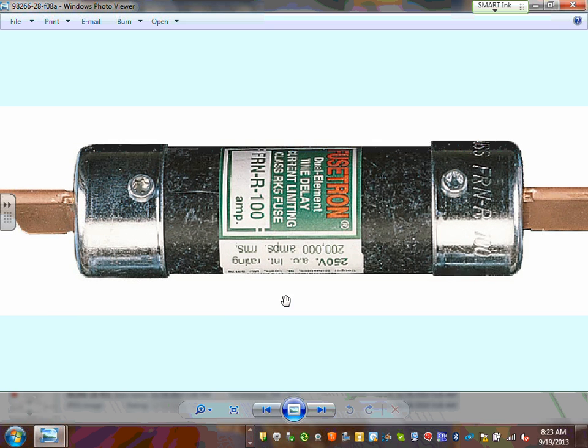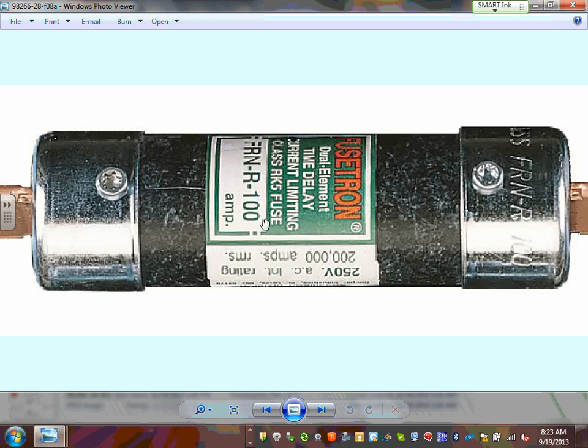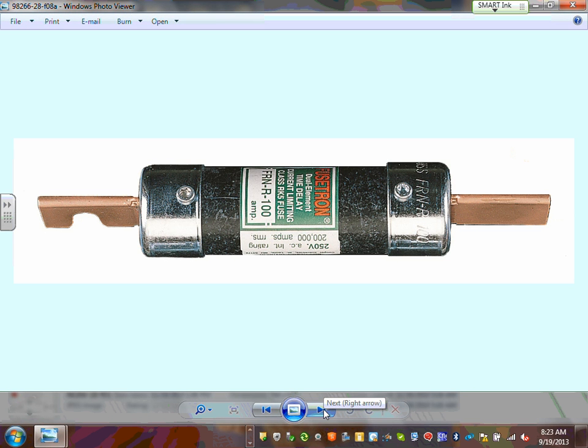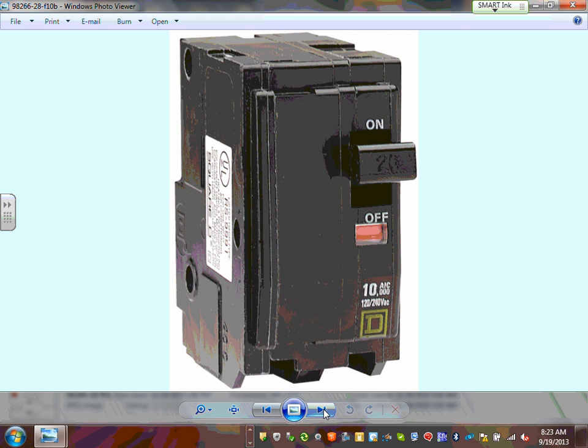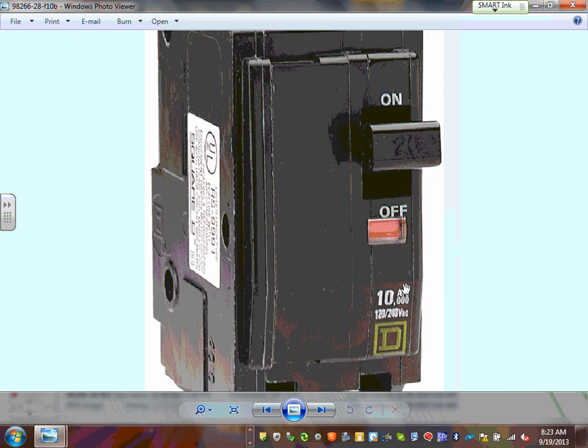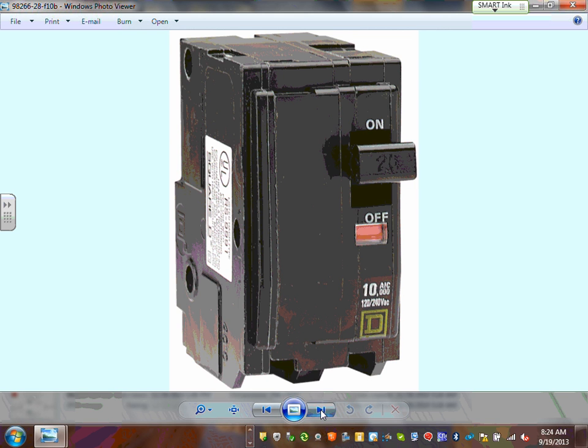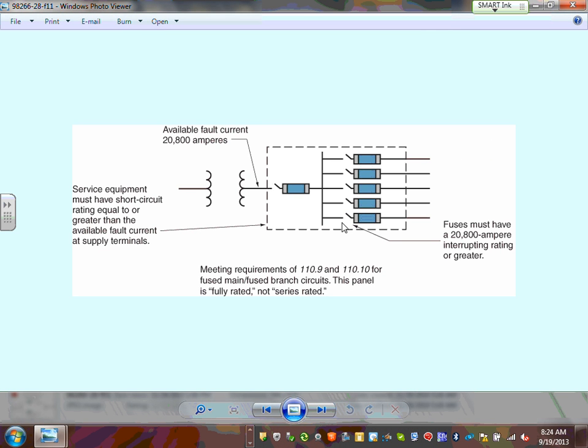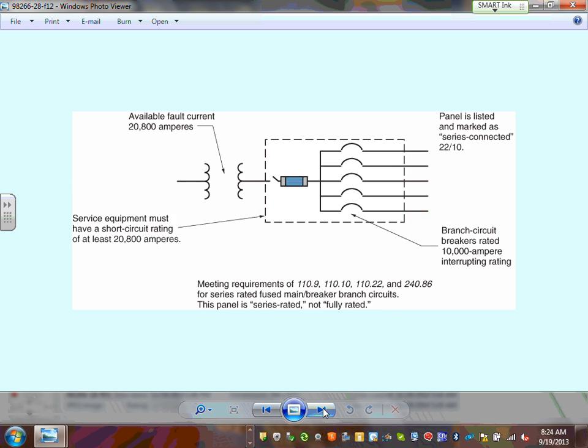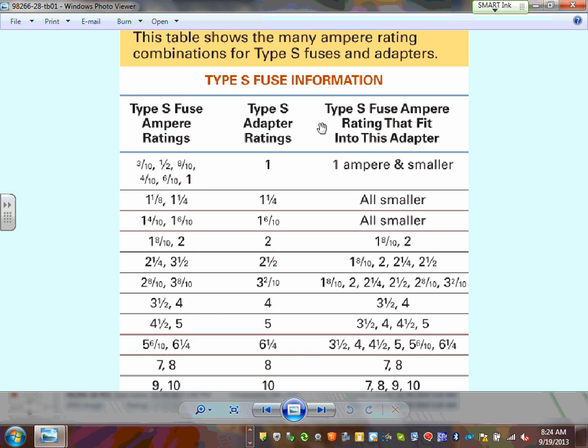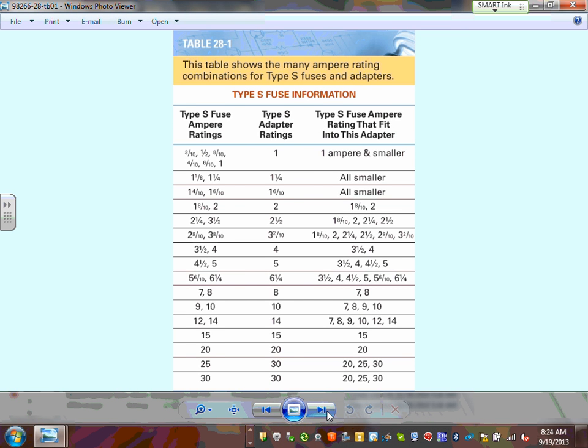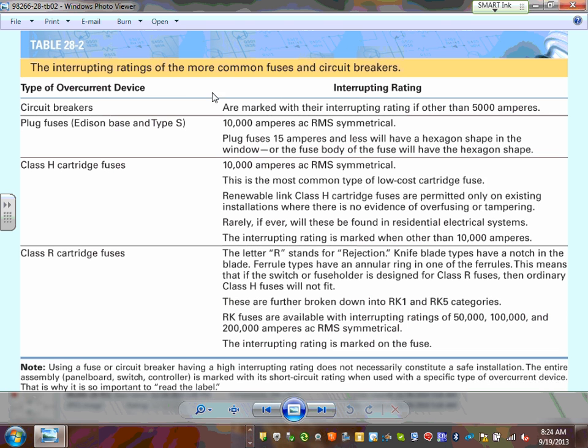Different plug-in fuses include cartridge fuses rated for 250 volts and higher interrupting ratings. Circuit breakers come in single-pole and two-pole, which is what we typically use. Look at the interrupting rating — it's printed right on the breaker, often 10,000 amps. Fuses can interrupt up to 200,000 amps; circuit breakers typically max out at 85,000 amps.